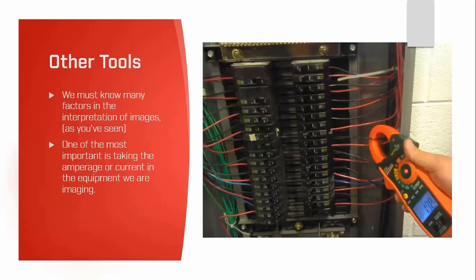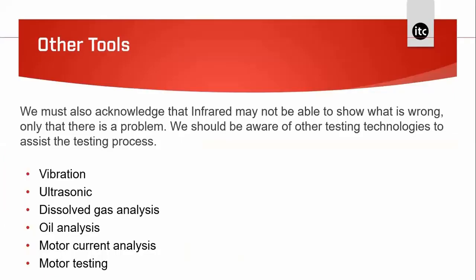There are other tools in the toolbox. One of the most important is taking the current reading of the equipment you're imaging. Also be aware that infrared may not be able to show what is wrong — only that there is a problem. Other testing technologies to assist include: vibration analysis for motors, ultrasonic for air leaks or arcing, oil analysis for transformer oil, and motor current analysis. Thermography is excellent at finding a problem, but we may need other tools to understand exactly what that problem is.